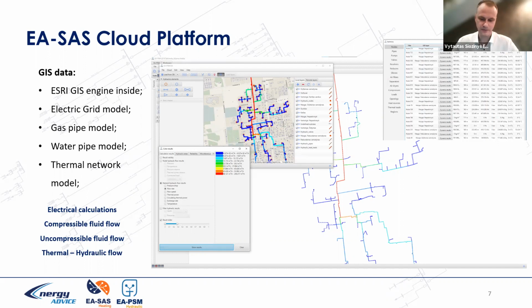I mean that the consumer requires some energy and some temperature at the consumer connection to the district heating side, and the thermal hydraulic calculation, according to forecasted energy consumption data, calculates each hour the optimum temperature output from the boilers connected to the district heating company, the optimum temperature output and required energy output.